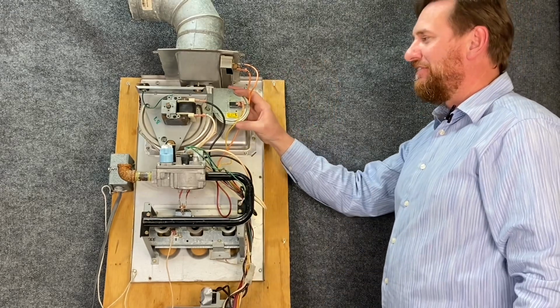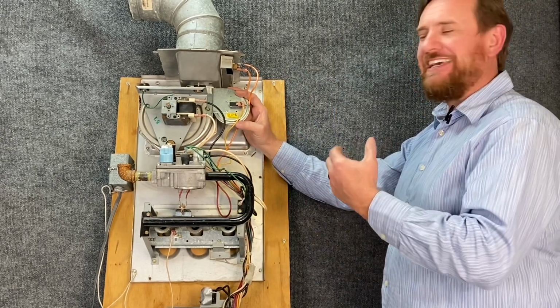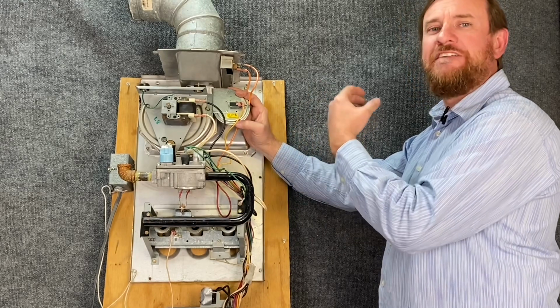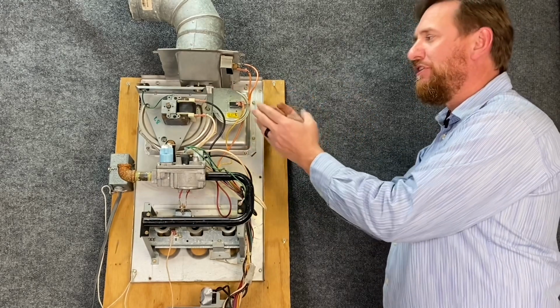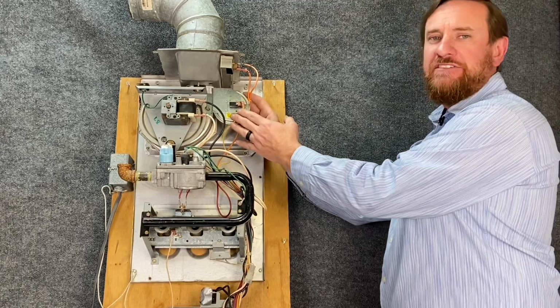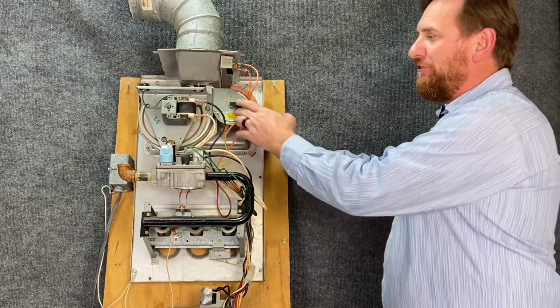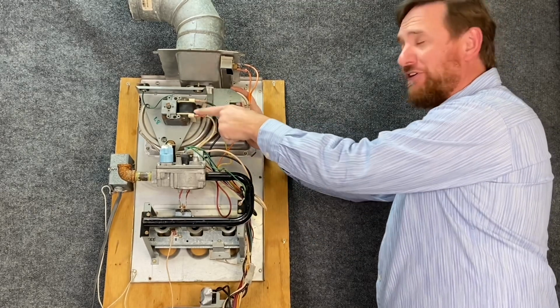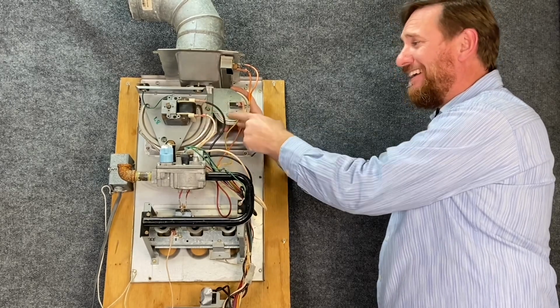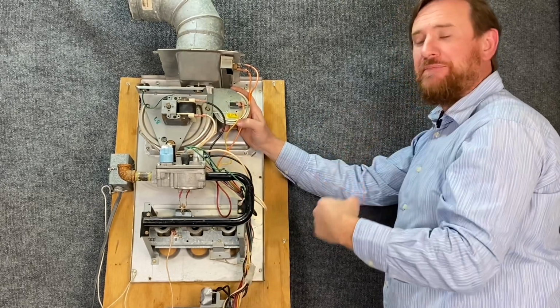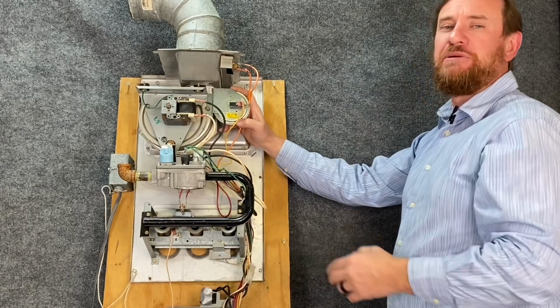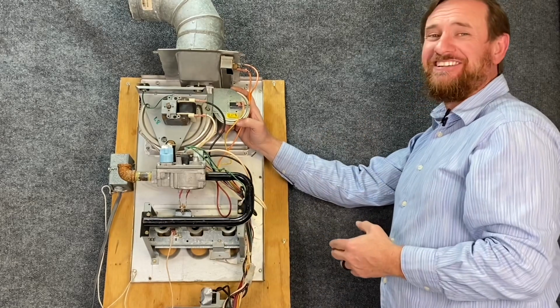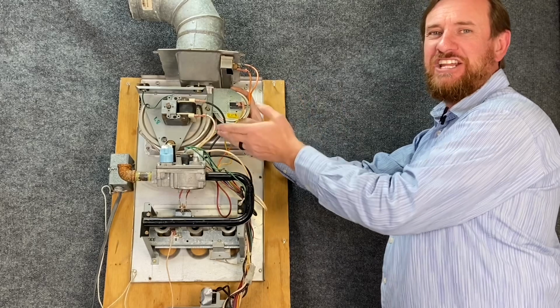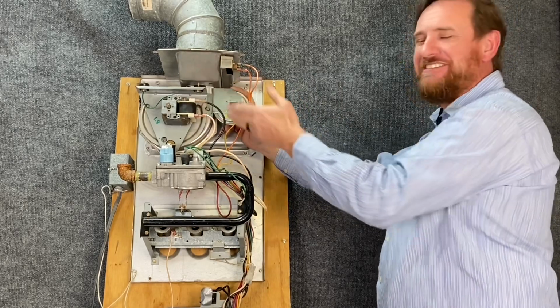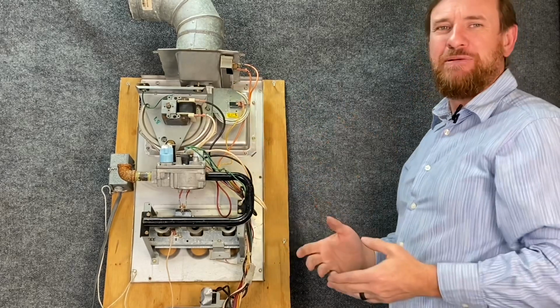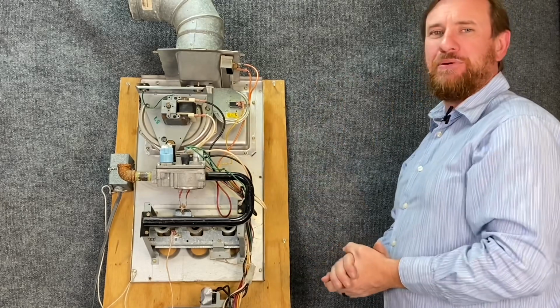So with my students, to make them understand, I have them say it as a negative pressure switch or a vacuum pressure switch, so they understood that it's sucking, it's pulling a draft against the switch. Its job is to watch this motor, so to speak, to make sure it's doing its job. If this motor stops working, it tells the IFC, hey, we got a problem, and the IFC shuts everything off to make sure we're running safe. Some of my students call it a vacuum pressure snitch because its job is to watch the motor and snitch on it if there's a problem. However, you need to remember that it's a massively important safety feature.